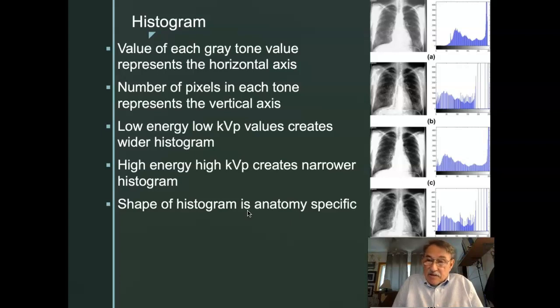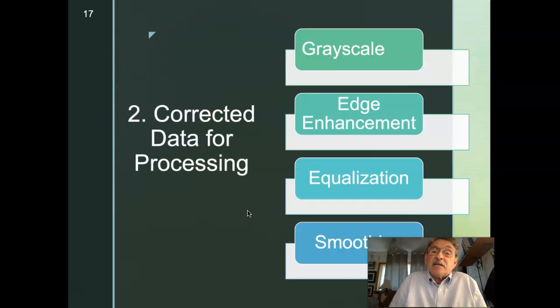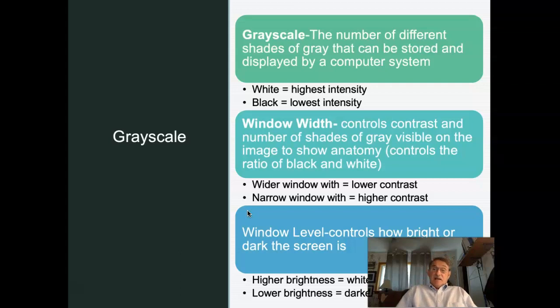We want to select the correct lookup table to process our image. If we select a sternum lookup table to process a knee x-ray, we won't get the expected results. The data must be corrected and prepared for processing and display.